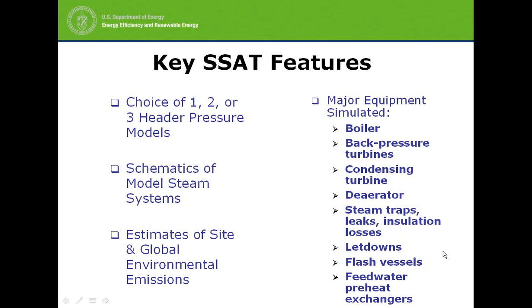Once it's built a model, it can evaluate steam system improvement projects. A lot of times we evaluate projects one at a time - what would be the impact if I put in a heat recovery system on the boiler, for example. But often you may want to evaluate multiple projects at the same time to see if there's a combinatorial effect, or if one project overlaps with another so you don't double count. It's a very powerful tool, allowing a lot of flexibility, and I've been using this for a long time.